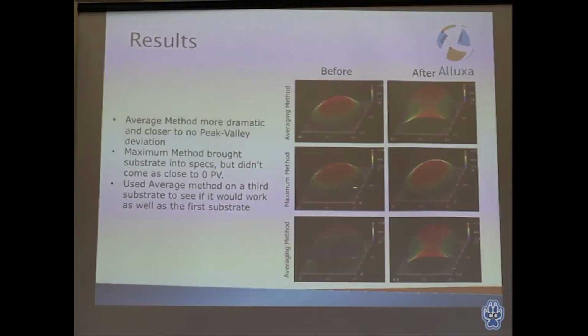The second one here, this one shifted a little bit, but not much. So this one, for the scale here, is plus 0.69 and minus 0.79, so it was pretty close to being within spec. It was just a little bit out. So I tried the maximum point for the variation for the PV, and I used my other process using the maximum method for this one. And this only changed to 0.52 and minus 0.25. So it still ended up being within specs and actually is, again, in inventory for the customer.